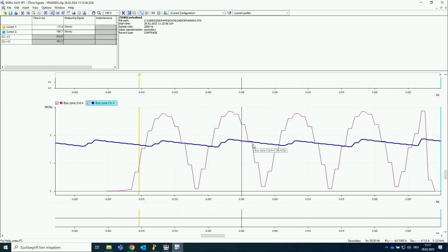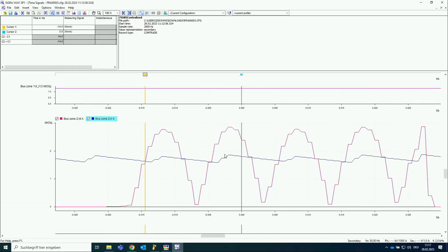And we see here, not the beginning of the fault, but when the differential current really starts. Then the 2 out of 2 algorithm will be triggered when we have the first threshold exceeding. Maybe we can go step by step. Here we have the first possibility, and here a little bit on the right side, to be a little bit more realistic. And now we will start the 2 out of 2 algorithm. If you remember, for the 2 out of 2 algorithm, 1 threshold exceeding is enough.